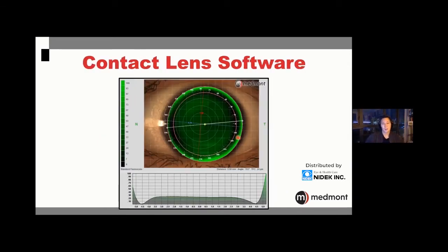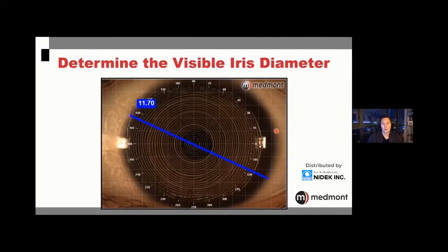This is where we use the Medmont contact lens software — a tool that lets you take your highly accurate map and place a rigid contact lens on top of that topography. You can optimize the fit, diameter, apical clearance, landing, and edge lift, so that you place the right first lens on the patient the first time, making you more efficient in practice. The first step is measuring visible iris diameter. For those who have had the Medmont E300, you'll now notice a color image to assess the borders of the visible iris, plus a wider field of view.